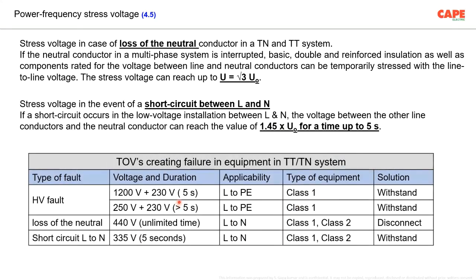So basically, I put these stress voltages in this particular table. TOV is creating failure in equipment in TT and TN systems. Type of fault is the high voltage fault, for example, 1200 volt plus 230 volt up to 5 seconds. This is applicable between line to P, meaning the protective earth, applicable for class 1 equipment, of course, because class 2 and class 3 equipment doesn't have a protective earth or doesn't need a protective earth. So L to P, class 1 equipment, your equipment must be able to withstand that particular voltage. 250 volt plus 230 volt for a time greater than 5 seconds, line to P, applicable for class 1 equipment, your equipment is supposed to withstand that particular voltage.